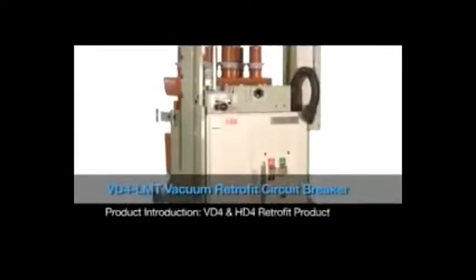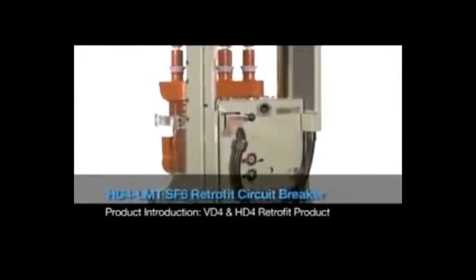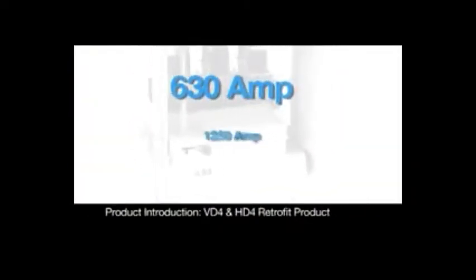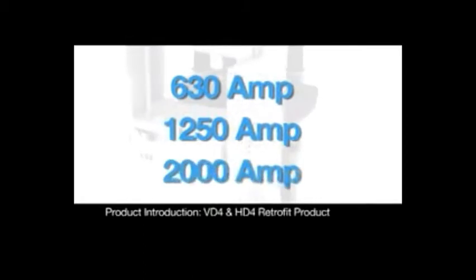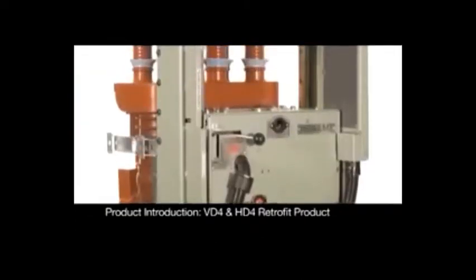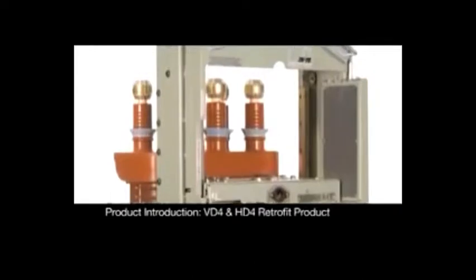The VD4 and the HD4 circuit breaker that ABB develops here is a basic retrofit replacement that we use to replace the old type circuit breakers in the Reyrolle type switchgear. We offer a number of standard ratings, which are 630 amp for normal current, 1250 amp, up to 2000 amp. They'll be used at airports, power plants, supermarkets, the mines specifically. So they cover a very wide variety of clients all over the markets.